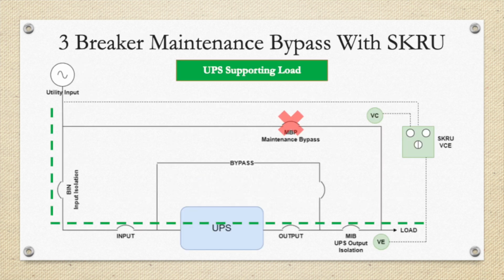On the very next drawing, we're going to show a 3-breaker maintenance bypass with a solenoid key release unit, SKRU, interlock. SKRU Kirk key interlocks are essential, in my opinion, for any maintenance bypass. What does it do for you? It will not allow you to operate the maintenance bypass breaker until such time that the SKRU control unit gets a signal from the UPS that it's in internal bypass.